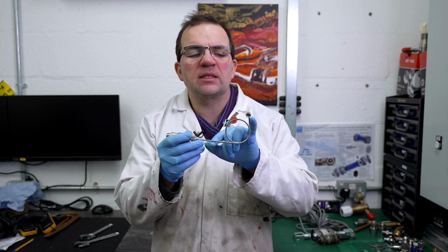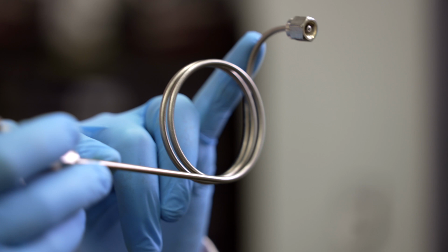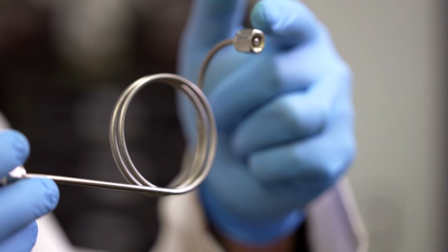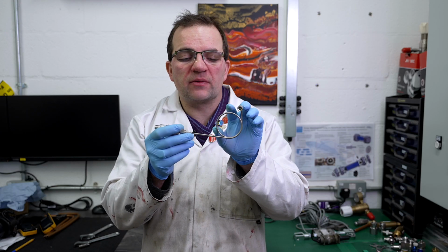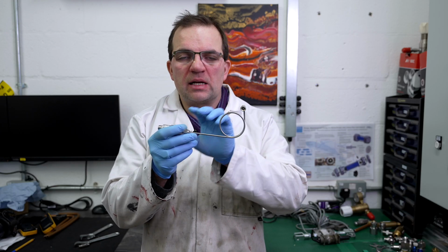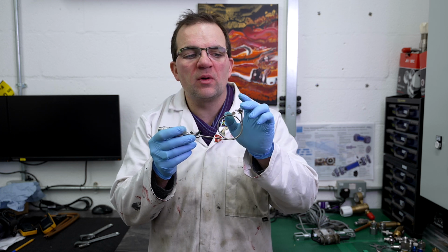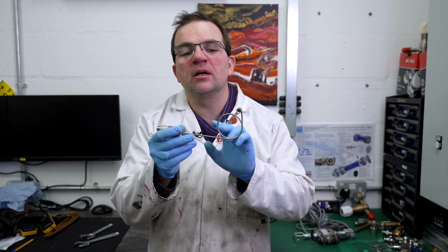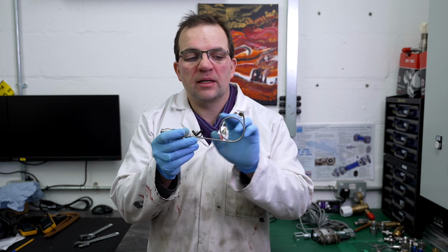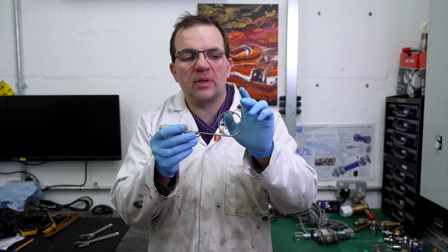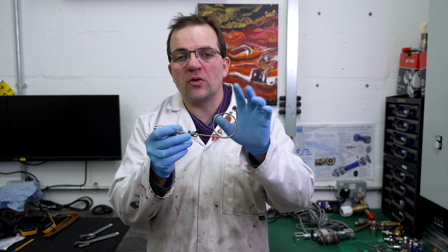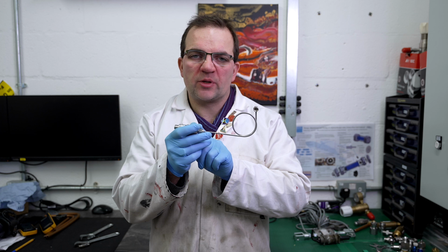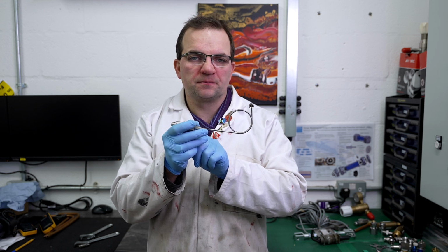Also, because there is a long distance, this is a trapped volume of gas, and it's very hard for the gas to move all the way up and around, so it effectively becomes an insulator. It can still transmit the overall pressure through all the gas in here, but in a way it cushions and insulates the hot temperatures of the combustion chamber from the pressure transducer itself.